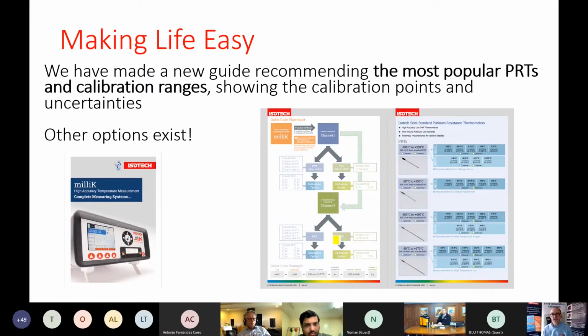So we want to make life easy for people because it can be quite complicated figuring out the ranges. So we've made this new guide, and we're recommending the most popular PRTs and the calibration ranges. So we've got a flow diagram, and that will help us identify which probe we might want to use. And then as we determine which probe, we put in here the calibration points and the uncertainties, so the customer can see what they can expect over different ranges.